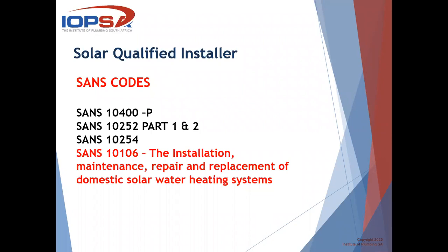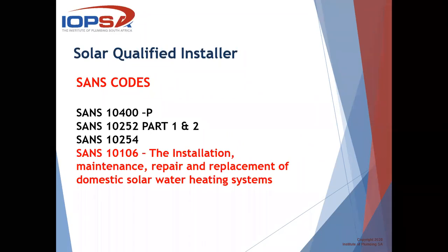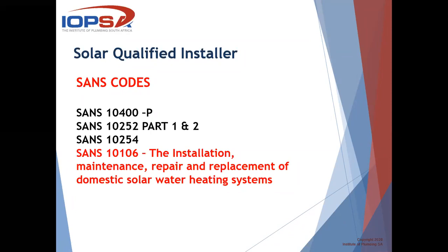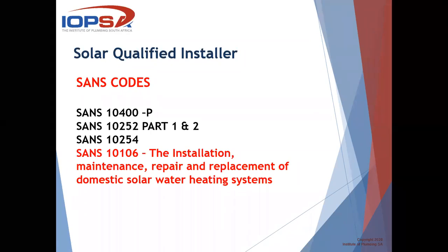If a geyser tank is in any way, shape, or form connected to a solar collector for the purposes of issuing a COC, that is then classified as a solar installation. So I think it's important that we understand that, and that we make sure that we don't overstep and we're not working on a system that we do not have the knowledge or the expertise on.